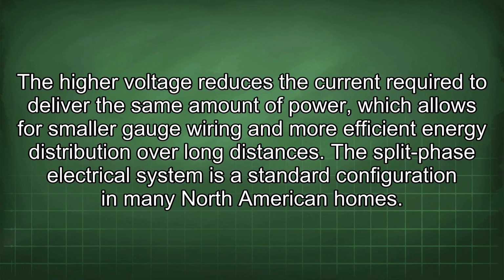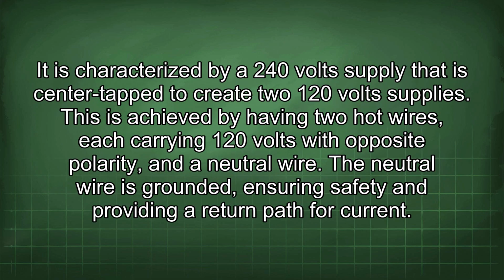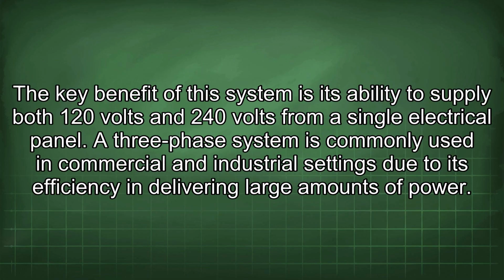The split-phase electrical system is standard configuration in many North American homes. It is characterized by a 240-volt supply that is center-tapped to create two 120-volt supplies. This is achieved by having two hot wires, each carrying 120 volts with opposite polarity, and a neutral wire. The neutral wire is grounded, ensuring safety and providing a return path for current.